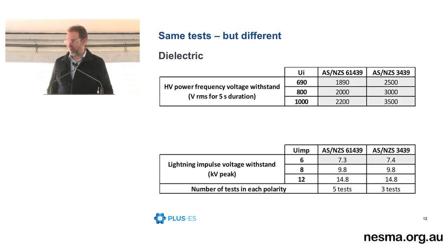Dielectric is pretty simple. It's not simple, but you apply a test value. You have a test voltage that you use to verify a certain Ui or Uimp on the switchboard. So the values have changed. The 3439 values have reduced to come in alignment with the IEC. I've tried to highlight in grey. I don't know how clearly you can see it there, but you can see we have values for, say, the high voltage power frequency withstand test, and they're dropping from a previous test voltage of 3500 volts down to 2200 volts. So it's significant, but the duration is still 5 seconds. It's a pretty quick test.